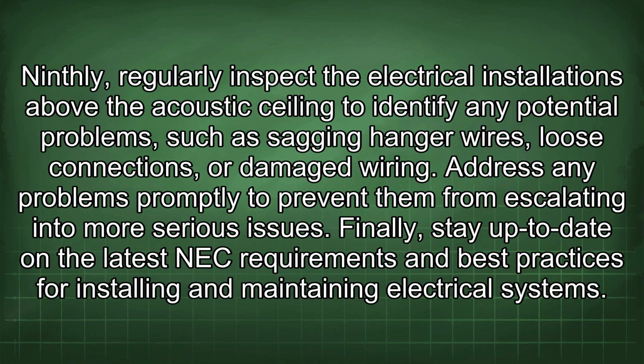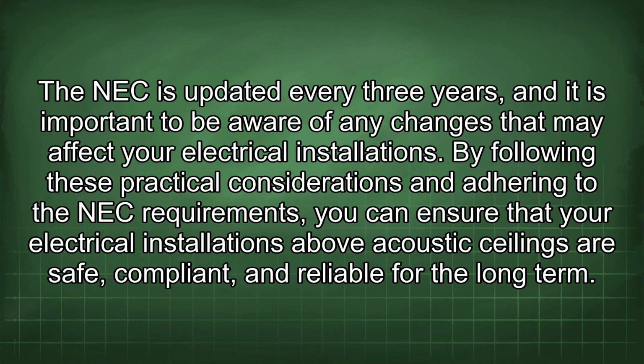Ninthly, regularly inspect the electrical installations above the acoustic ceiling to identify any potential problems, such as sagging hanger wires, loose connections, or damaged wiring. Address any problems promptly to prevent them from escalating into more serious issues. Finally, stay up to date on the latest NEC requirements and best practices for installing and maintaining electrical systems. The NEC is updated every 3 years, and it is important to be aware of any changes that may affect your electrical installations. By following these practical considerations and adhering to the NEC requirements, you can ensure that your electrical installations above acoustic ceilings are safe, compliant, and reliable for the long term.